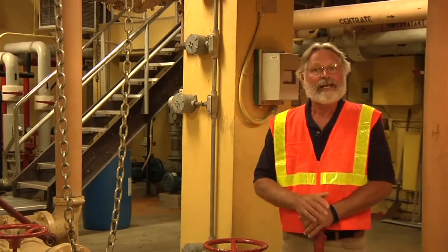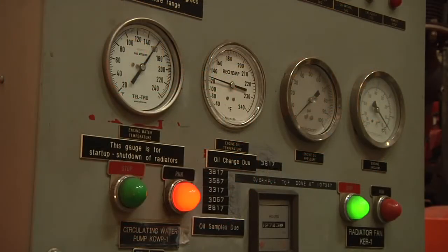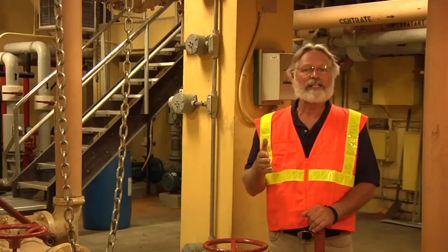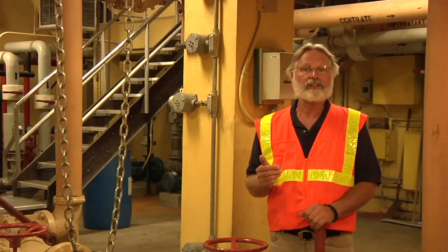But during that process, we also generate some methane. That methane gas we can use to run generators, and those generators power part of our wastewater treatment plant. They also generate waste heat, which we use to heat up the digestion process. So it's a nice circle. We use a whole lot of the energy that's stored inside that sludge to make our process cheaper to operate.